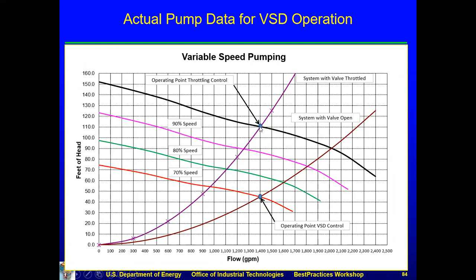Well, they managed to reduce the flow to what they needed, but they didn't do it very efficiently. Because if I open that valve up and slow the pump down, I can operate here instead of here. Look at the reduction in pump head. That's what, 45 versus 110? You think that's going to save some energy? Daggum right. It's going to save a bunch of energy.